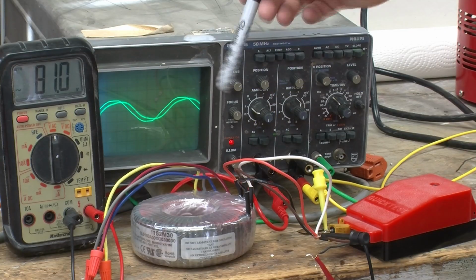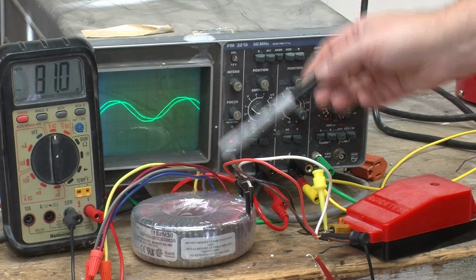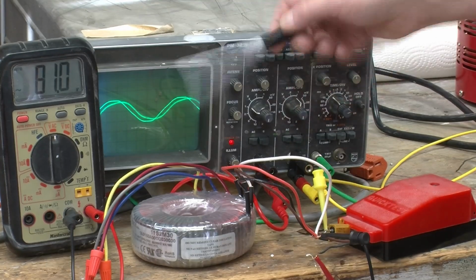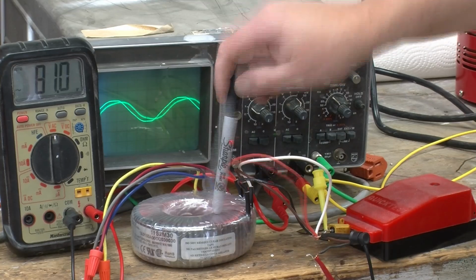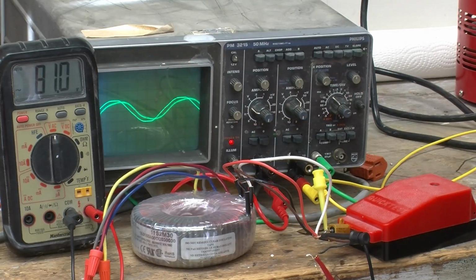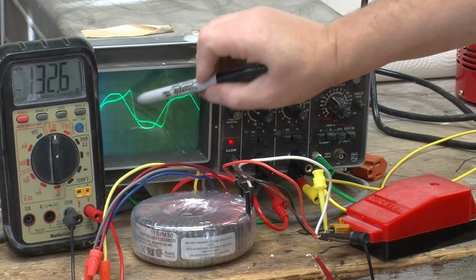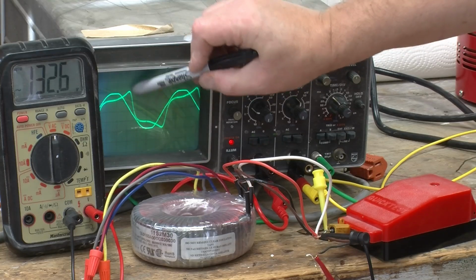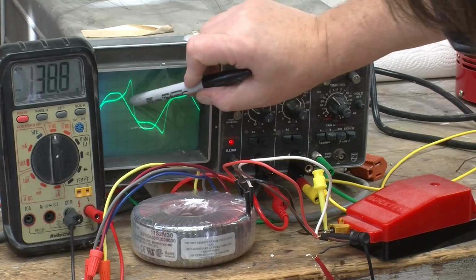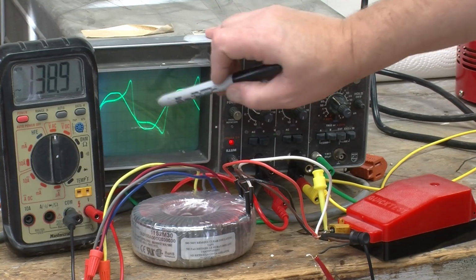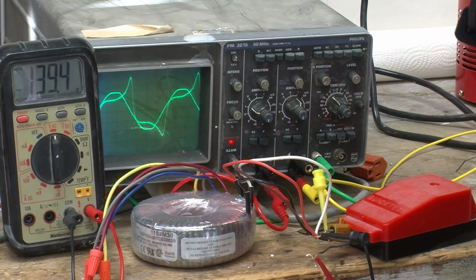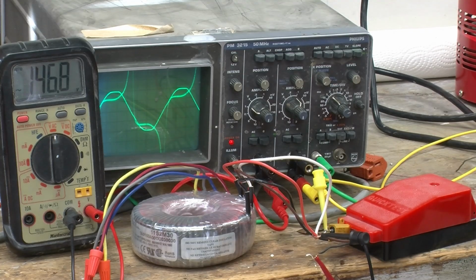So what's essentially happening is we apply a certain voltage to the primary, and for that voltage to be countered by a voltage generated in the core, we need to draw an appropriate amount of current — that's the current we see on the slightly lagging trace. As we increase the voltage, because of saturation, at certain points in the curve we have to draw an absolutely huge amount of current. In this case it's only maybe 10, 20, 30 milliamps, but in a bigger transformer this could become a real problem, or if we push it further into saturation.